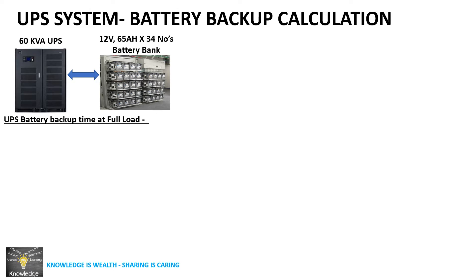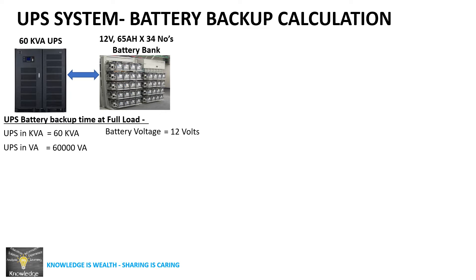Let's calculate the UPS battery backup at full load. The UPS capacity is 60 kVA. In volt-ampere, we multiply by 1,000 — so 60 into 1,000 equals 60,000 volt-ampere. We know each battery voltage is 12 volts, and 34 batteries are connected in series, so the battery bank voltage is 12 × 34 = 408 volts.